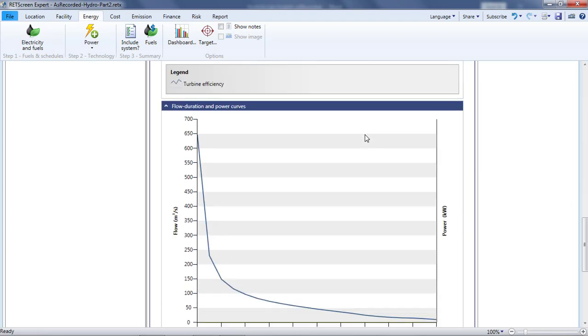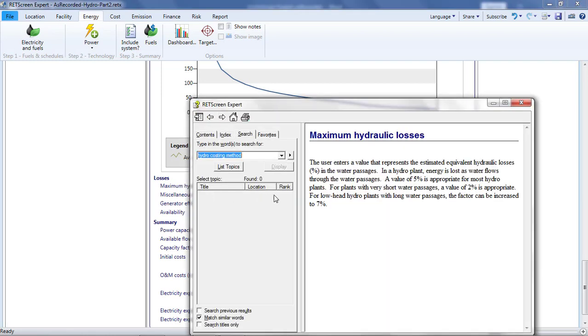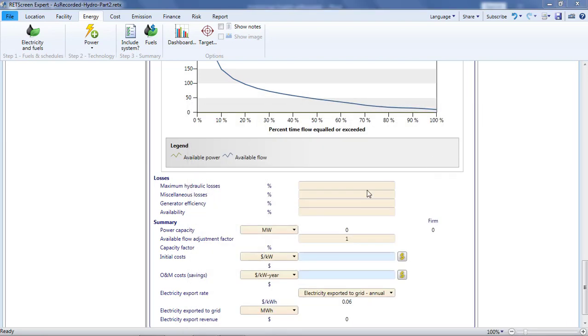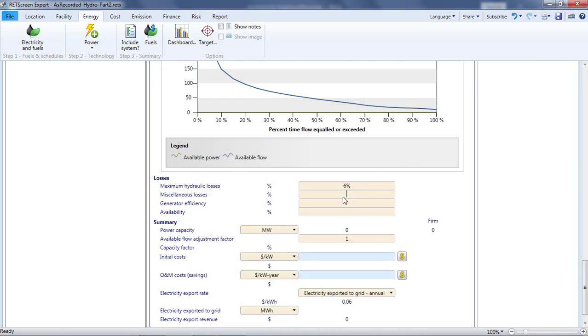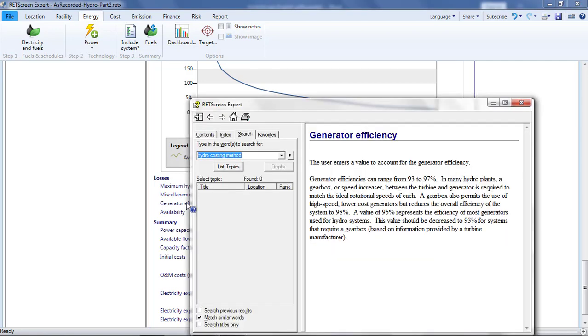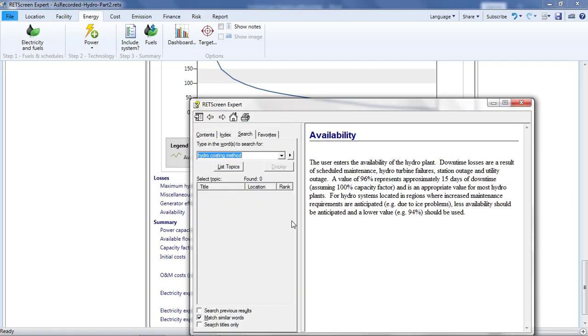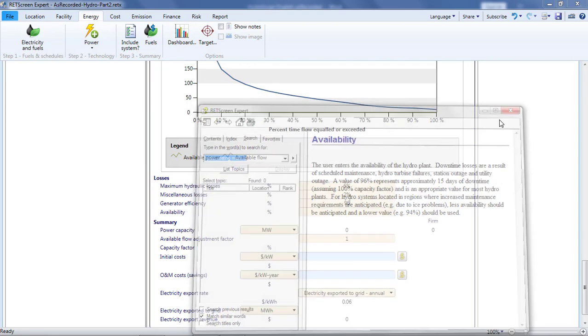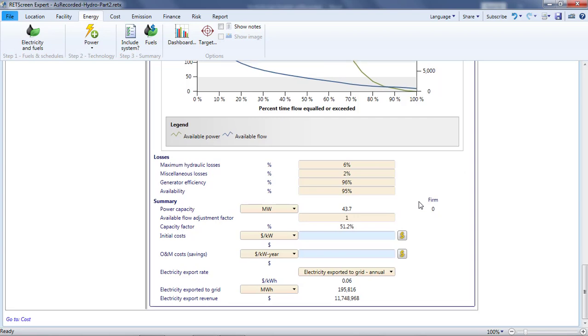Below the graphics, there is a section where losses beyond those reflected in the efficiency curve can be specified. RETScreen's help is useful, both for understanding what these losses refer to and for picking reasonable estimates for these losses. The hydraulic losses refer to how the water passages resist the flow of water and therefore reduce the power that the turbines can produce. I'll enter 6% here. Miscellaneous losses include transformer losses and parasitic electricity losses. I'll enter 2% here. For the generator efficiency, I'll enter 96%. The availability refers to the percentage of the time that the plant is in such a condition that it can generate power, should flow be available. The remainder of the time, maintenance, grid outages, or equipment failure prevent operation. I'll put in 95%, a relatively low value, because this project may be affected by ice.